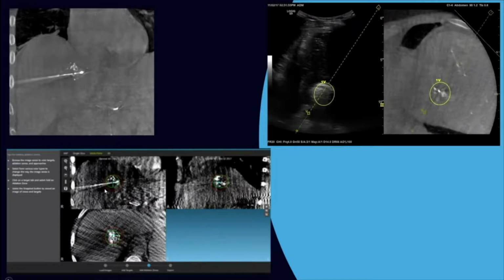This zone of ablation is known for the Medtronic probe and is able to be programmed into the ultrasound, so you can get the same zone right on your ultrasound, and it overlays on your CT as well. So you can turn this on or off. This can be manually programmed in for any of the ablation devices that are out there, as long as you know what the device is and what its predicted zone of ablation is. That's what the graphic will represent on the ultrasound machine.